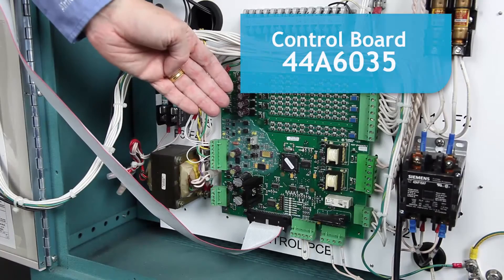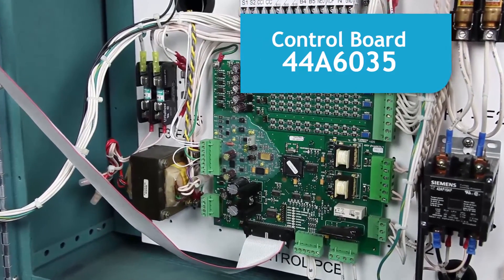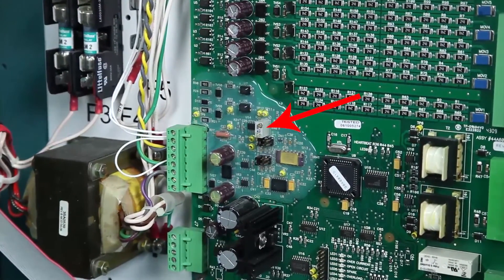Controller Board 44A6035 is used for control of ADB-CCF and CHF regulators. It uses a single potentiometer to adjust the current at the highest step, which is B5 for a 5-step regulator or B3 for a 3-step. The output current for the remaining steps is set automatically. Overcurrent protection is also performed automatically, so no further calibration is required.